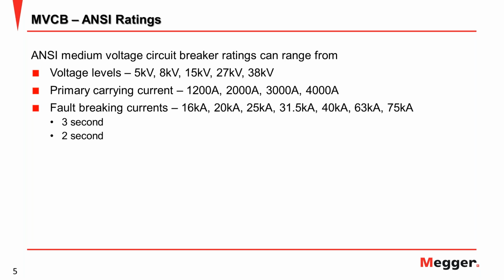Now this is the MV breaker based on the ANSI rating. There are three conditions based on the voltage level, primary carrying current, and fault breaking current. Based on the voltage level, there are 5 kV, 8 kV breakers, 15 kV, 27, and 38, maybe more. In other cases you can find other voltage levels.